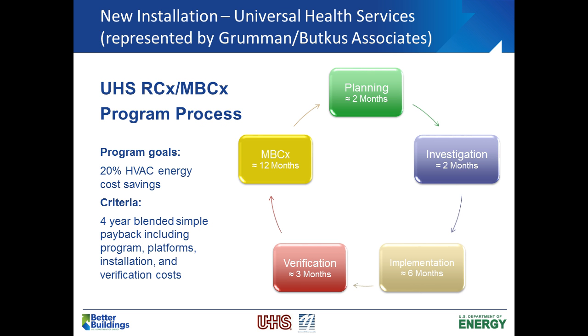We actually stroke valves. It's kind of like a true commissioning process of their equipment. We'll stroke valves and actuators and dampers, test the sequence of operations on the air handlers and the chiller plant, and make sure that if there are any kind of O&M or maintenance type issues that need to be addressed, we can identify those and work with the facility.